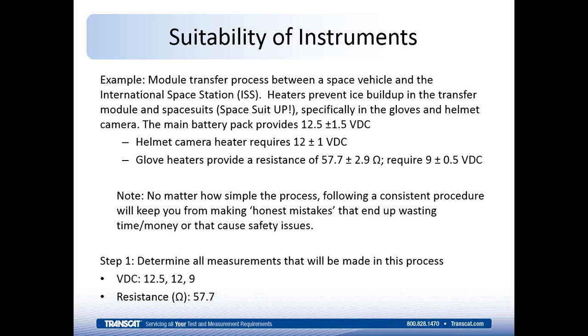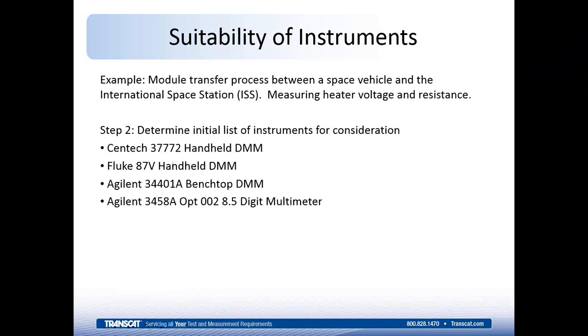So summing up, in step one, you would determine what are all the measurements that need to be made in the process. And here we're listing 3 different voltages and a resistance value. Step 2 would be to collect a list of instruments that you're considering to make those measurements. So here we're listing 2 different handheld multimeters, 1 benchtop multimeter, and a long-scale DMM.